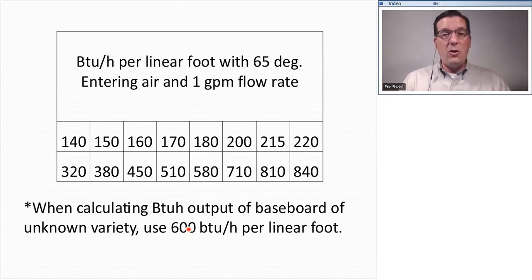And when you're going back and trying to reverse engineer what somebody was thinking 15 or 20 years ago when they made this repair or made that change or installed this new boiler, this can be part of your bag of tricks: measure all the baseboards, multiply the feet by 600, and lo and behold, that may be why that boiler size is there. That may or may not be appropriate. I'm not going to get too deep into that because that's a little more advanced for this kind of early course. But those of you who've been doing this a little bit longer, we should be sparking some recognition to say, he's got something there.